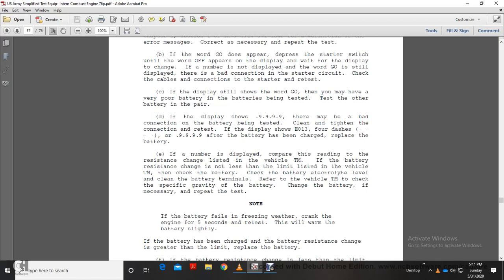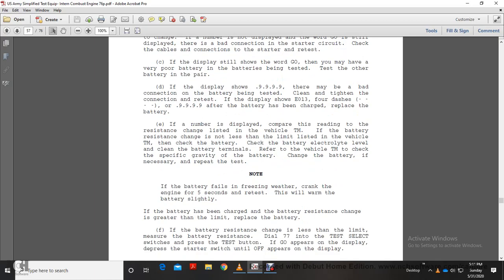If the battery display shows four nines, there is a bad connection on the battery being tested. Clean and tighten the connection. Retest. If the display shows E013, four dashes, or quadruple nines after the battery has been charged, replace the battery. If the number displayed is comparable to the reading of the resistance listed in the vehicle TM, check that the battery resistance is not less than the listed limit for the vehicle in the TM.